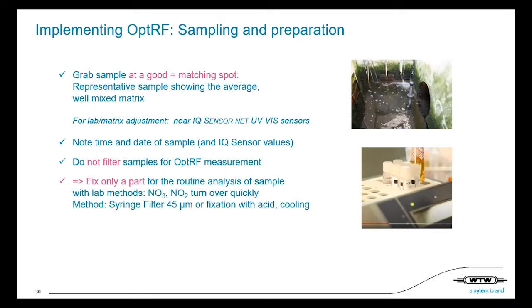Do not filter samples. You directly put the sample into the cuvette and take only a part of your sample to be fixed, meaning cooled or with acid, or filtered with a syringe. Because for your lab routine, you need to follow the guidelines for lab routine, which means for nitrate and nitrite, as they turn over quickly, you need to fix the sample, cooling or whatever it is, and measure it quite quickly, as usual. That's one of the things.